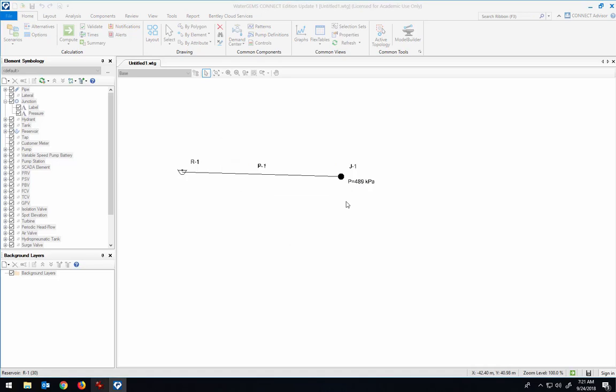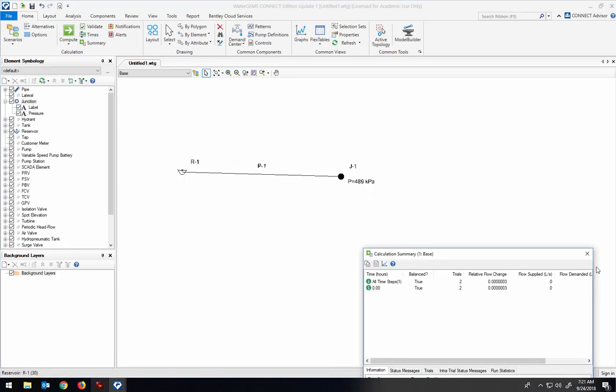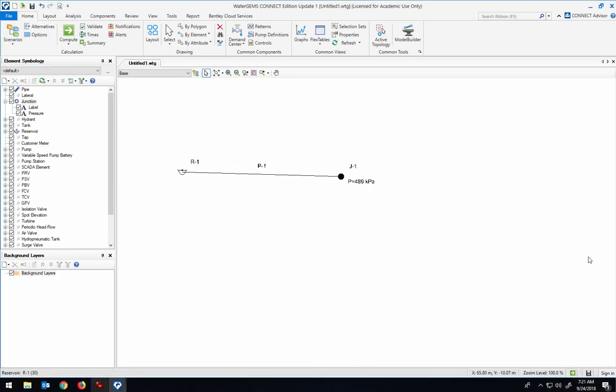If I compute, we see that we have 489 kilopascals, and that's what you'd get for using the hydrostatic equation if the reservoir is at 50 meters and the junction is at 0 and there's no head loss through the pipe. There's no friction in the pipe if there's no water flowing through it, so there wouldn't be any pressure decrease due to pipe friction.